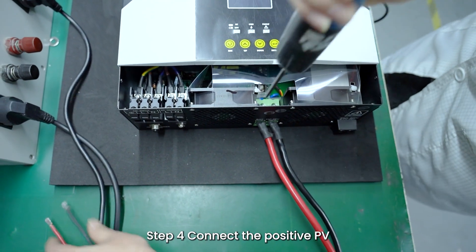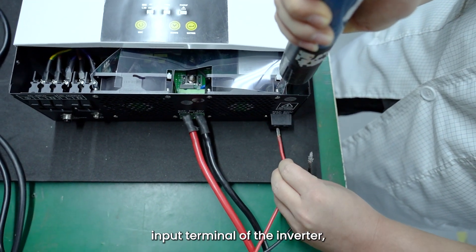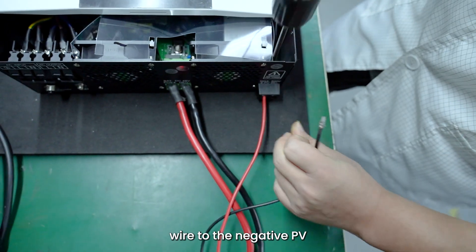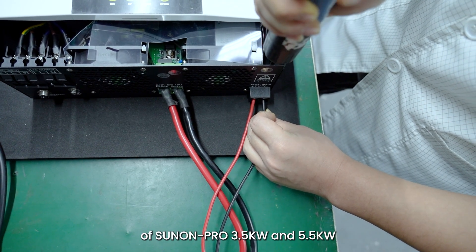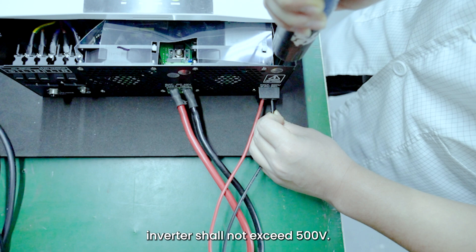Step 4: Connect the positive PV wire to the positive PV input terminal of the inverter, and then connect the negative PV wire to the negative PV input terminal of the inverter. Note: The PV input open circuit voltage of Sunon-Pro 3.5 Kilowatts and 5.5 Kilowatts inverter shall not exceed 500 Volts. The optimal operating voltage of the module is DC 40 Volts to 360 Volts.